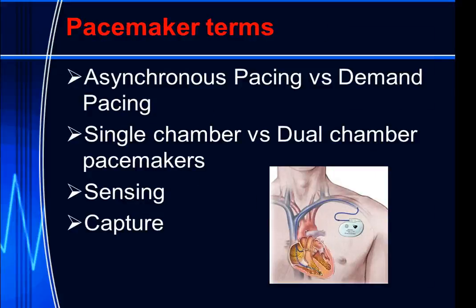There are pacemaker terms you need to understand. An asynchronous pacemaker delivers a stimulus to the heart at a set rate regardless of what the heart rate is. For example, if the pacemaker is set to 70 beats per minute and the person has a heart rate of 66 beats per minute, it will continue to pace at all times.